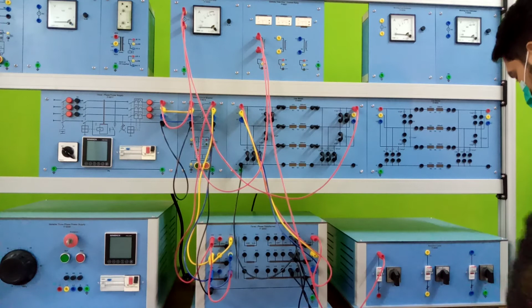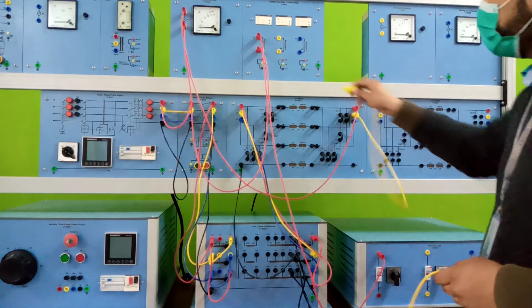This is how you connect the first phase, and now we come to the yellow phase. The other phases are connected the same way, in series. From the yellow phase of the transmission line to the definite time over current relay, and from the relay we connect the resistive load. That's the yellow phase done. For the blue phase, it's the same connection again.